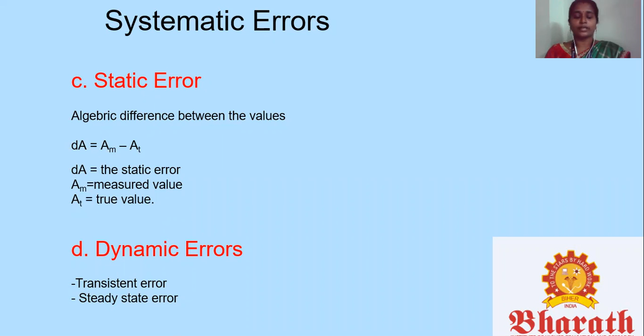The last one is dynamic error. It is defined as the algebraic difference between the indicated or recorded value of the measurement and its true value at any instant when the measurement is a function of time. Dynamic error has two components: transient error and steady state error. It is caused by the instrument's slow response in following changes in the measured variable.